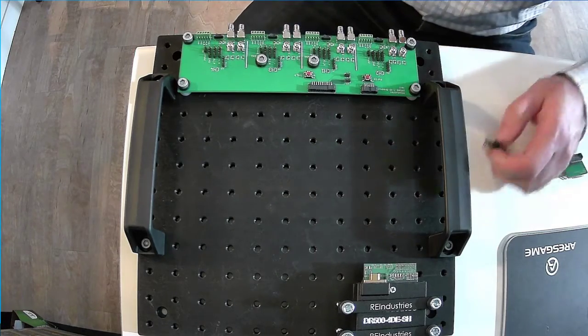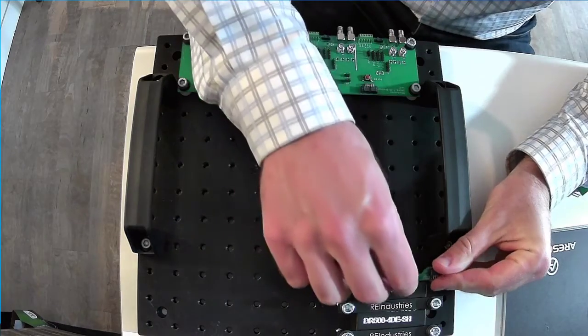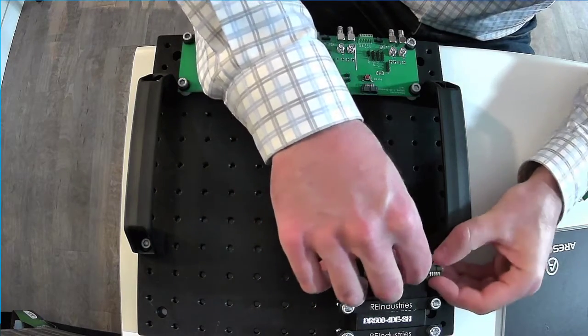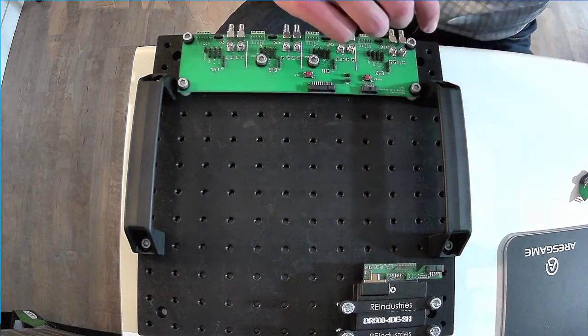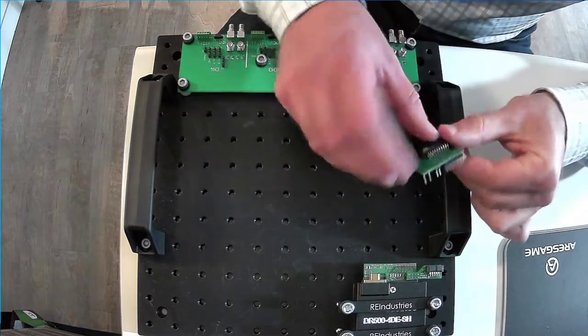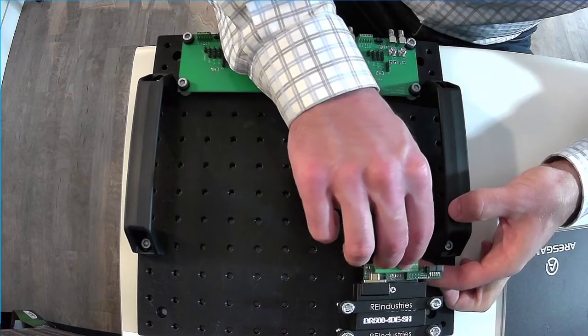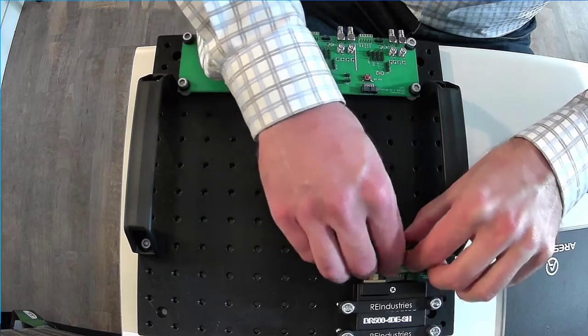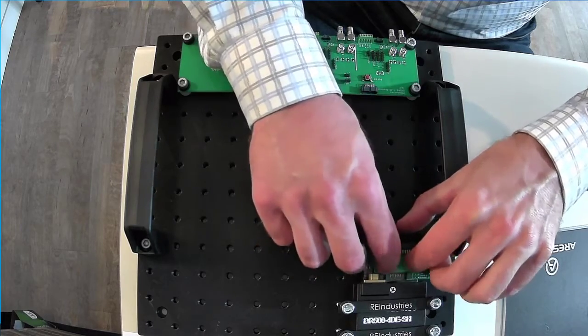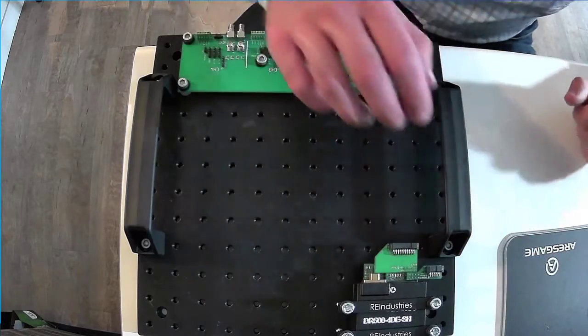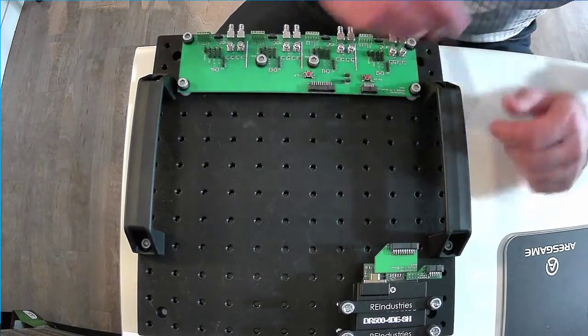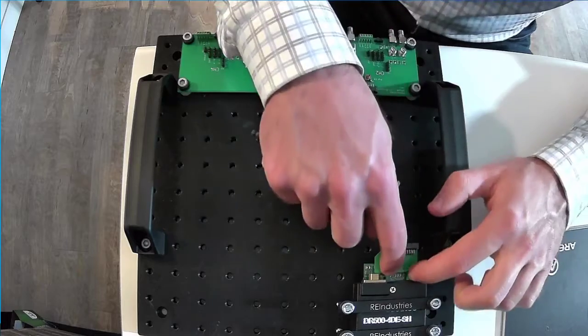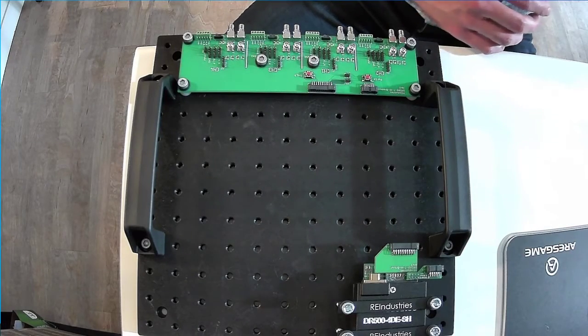So the first card is installed for the digital board and that's installed here. They're just through-hole headers on the bottom. This is a standard right angle connector with a matching cable harness. And then we install the analog card and these are a little snug. They're designed that way intentionally so just work it in carefully.